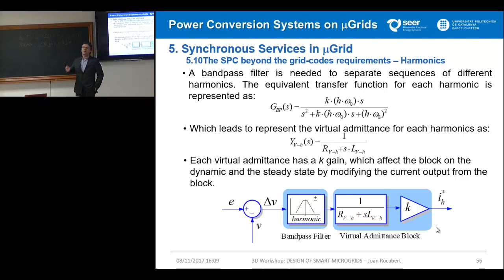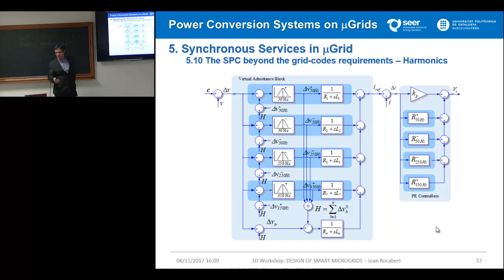Okay. Also, we impose the fifth harmonic, the seventh. In some cases, probably not, we are able to arrive until the 11th. Of course, we get the limit of the bandpass of the LCL filter, of the LC, of the line, of the grid connection line filter that you get. Okay, this is a maximum frequency that you are allowed to compensate.